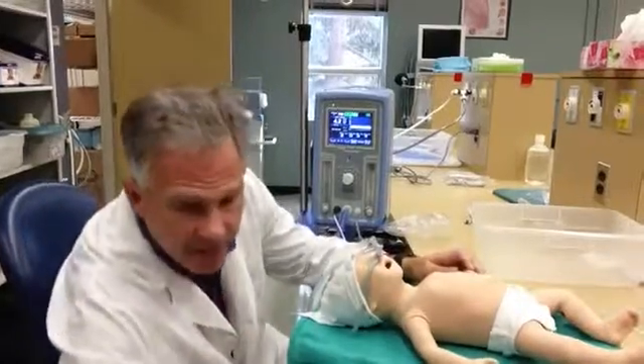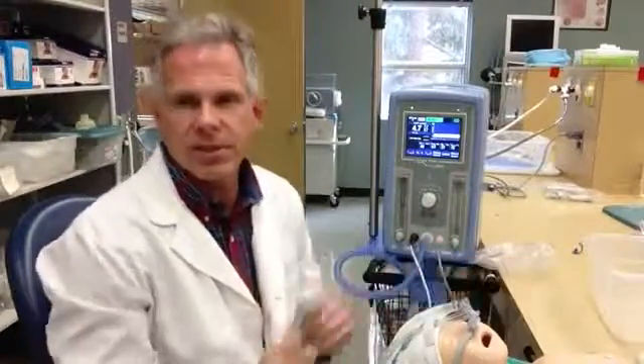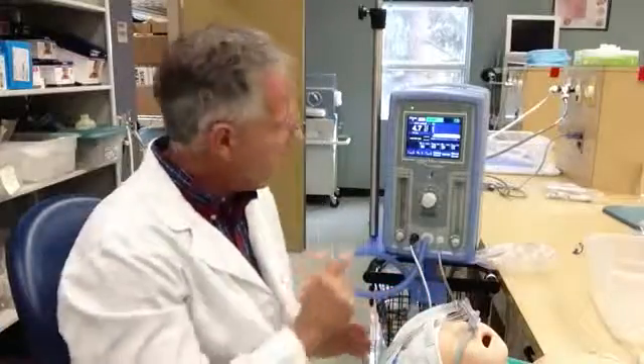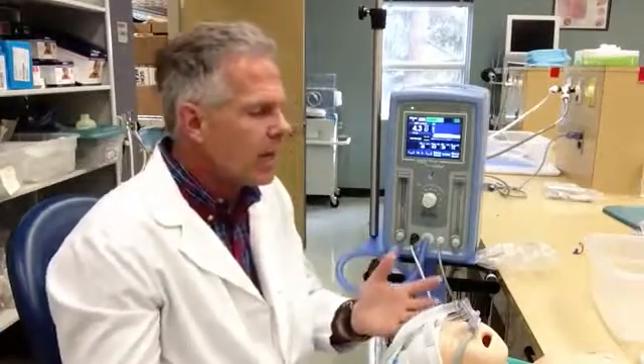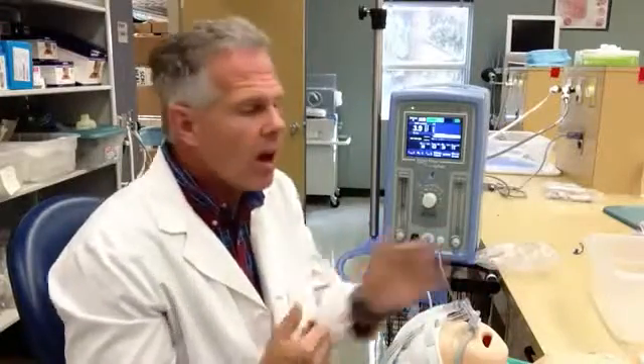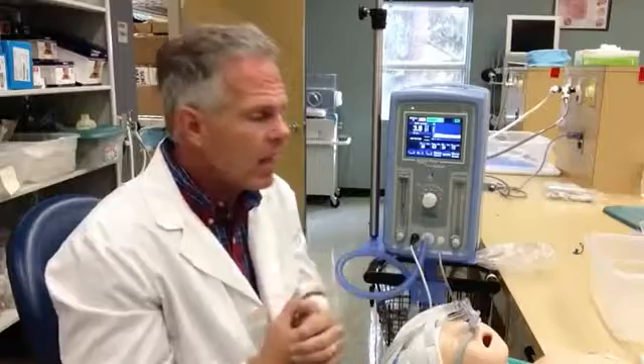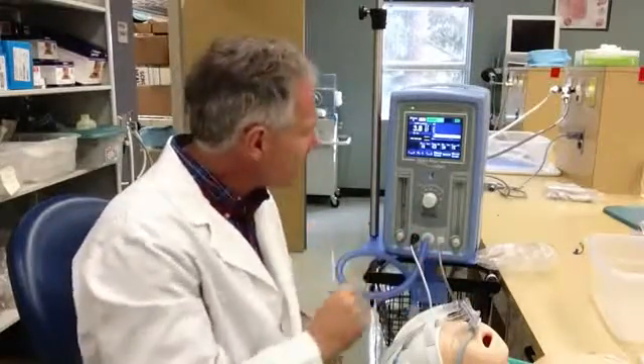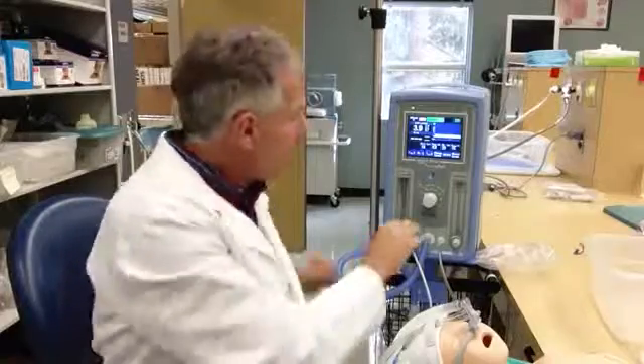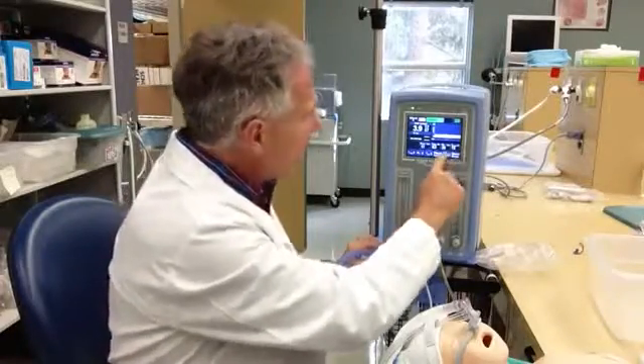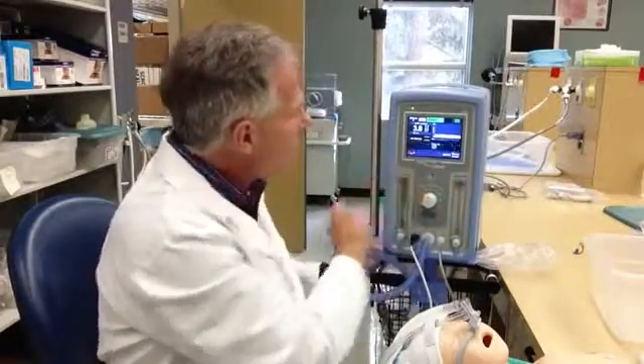Now, the limitation of this is that you need this little pressure sensor to make it work, and it's never worked very effectively. That's the problem. It can be moved, and any kind of movement by the patient can be triggered as respirations. Handling the patient, or if they're lying on it, sometimes alters the performance of it. So it hasn't seen a lot of clinical use. The number one use of this particular device, I'm going to switch modes here, is nasal CPAP.